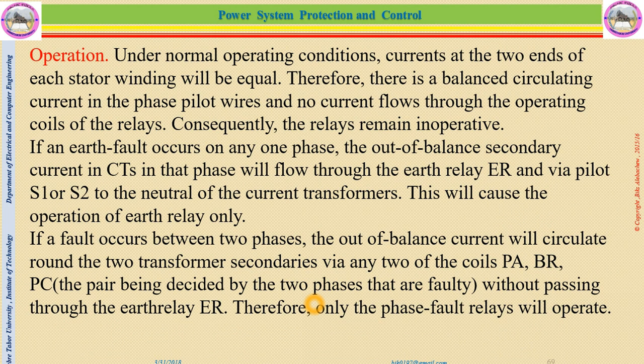Operation under normal operating conditions: the currents at the two ends of each stator winding will be equal. Therefore, there is a balanced circulating current in the phase pilot wire, and no current flows through the operating coil of the relay. Consequently, the relay remains inoperative. If an earth fault occurs on any one phase, R, Y, or B, the out of balance secondary current of the CTs in that phase will flow through the earth relay ER and via pilot wires S1 or S2 to the neutral of the current transformer.